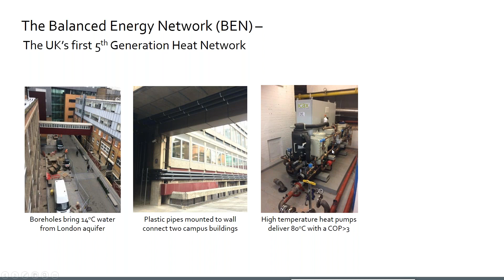It's a really interesting look at how you do that. What we were able to do was interface on the common header that the boiler circuit feeds, and we just replaced the first of the boilers with this in a cascade. Then all of the peak loads are picked up by the gas, and this takes as much of the load as we can. The COP for the individual units is still around 3, though the system efficiency comes down a bit for reasons we can discuss.